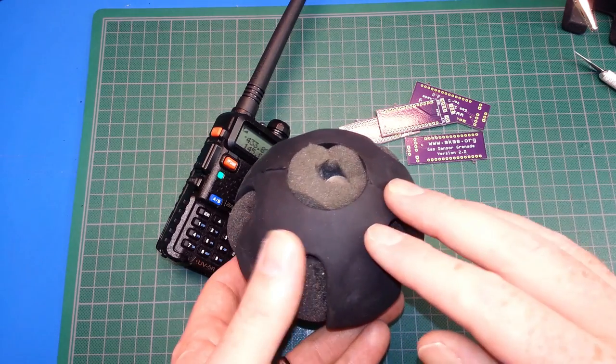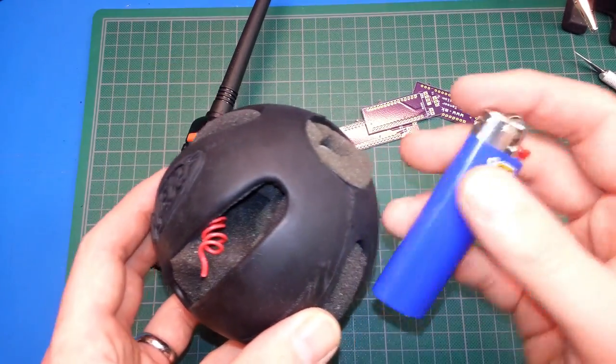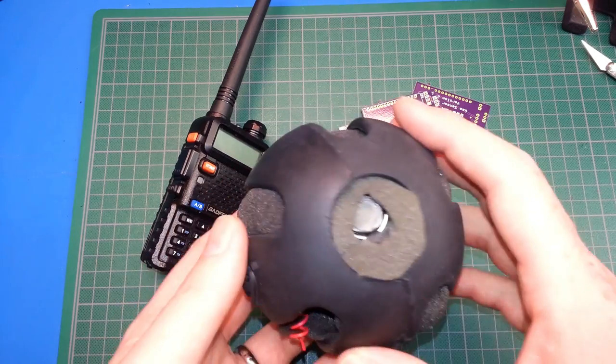You can see it alerted on CO as well as smoke — smoke alerted too. So it works well as a go/no-go, but the code does get confused when we give it a heavy dose of LPG. It works pretty well with smoke without too much problem.